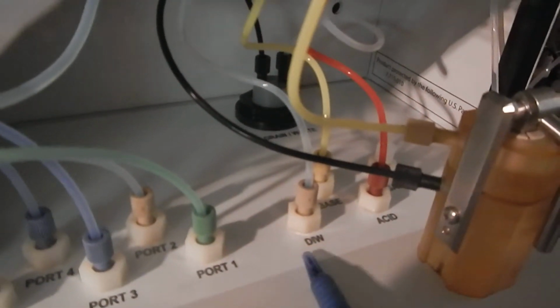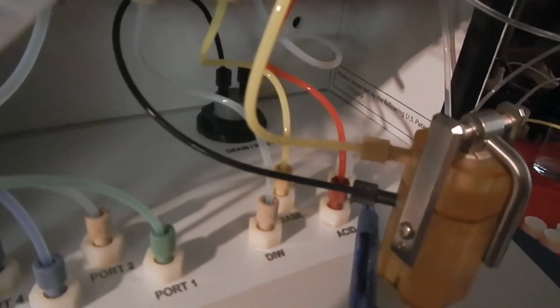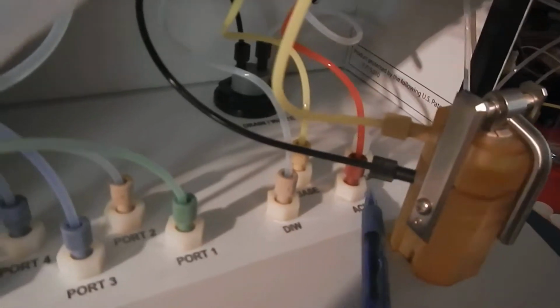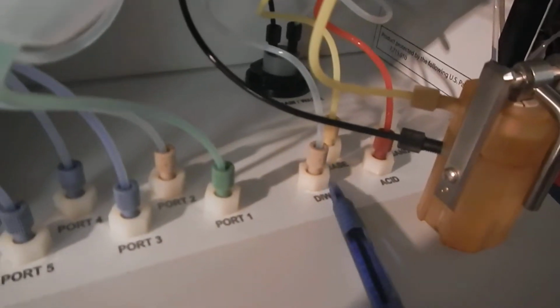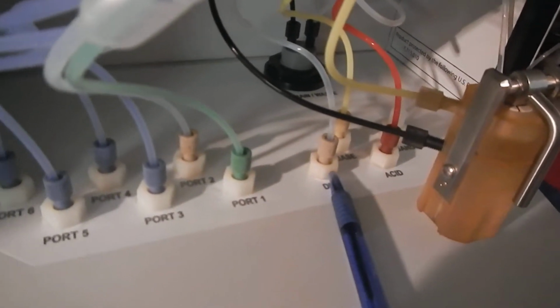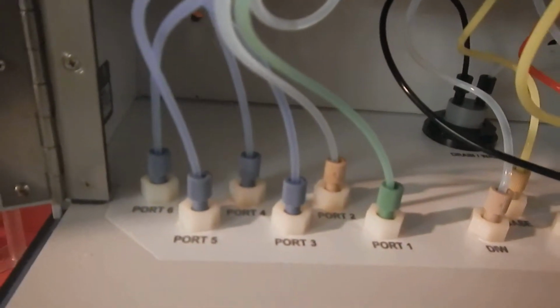The rest of the instrument has basically a number of ports. We have a ligand addition port at the back, which we're not using on this machine. This is a free cyanide machine currently. We have an acid port, a base port, and a DI water port. In the housing above the instrument, we incorporate a selection valve where we can access various ports.